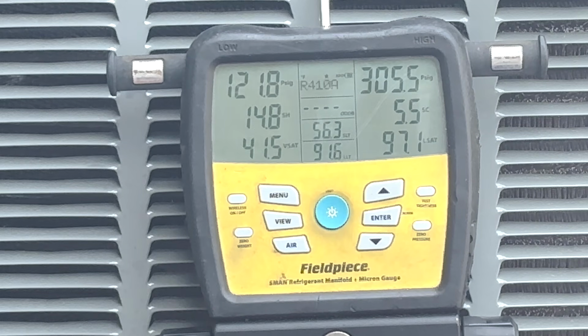And if I had a high subcool, right, and my superheat was dropping, well, that would kind of make sense if it stayed in that direction. But when it's fluctuating up and down, that's when the numbers just don't add up. The numbers should never constantly move.